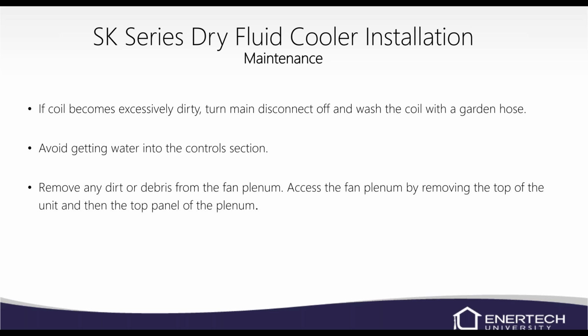Again, if the coil becomes dirty, cottonwood is a really bad thing, especially here in the Midwest. It will cause all kinds of problems. So you can wash it off with a garden hose. Obviously, don't get water into the control section, but that's on the side in its own little compartment. So put the door back on the electrical connections before you spray it out with water.